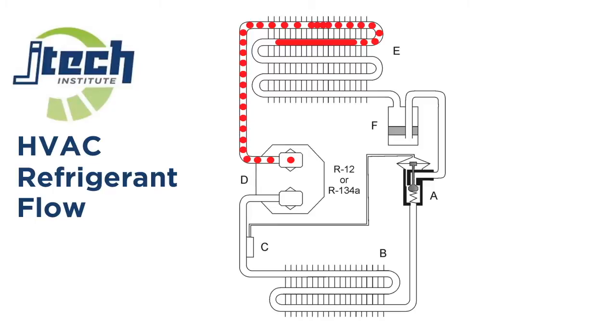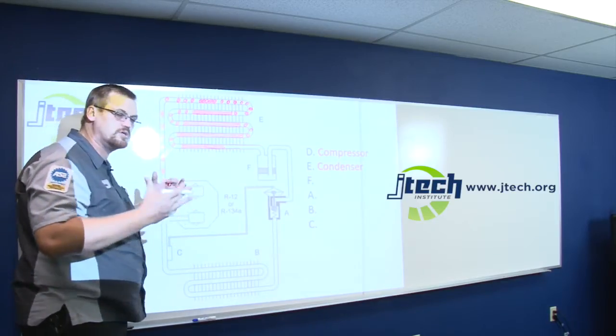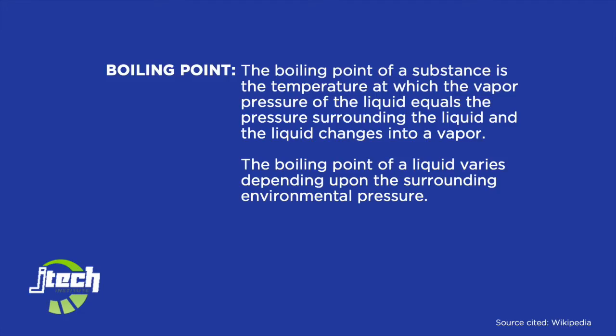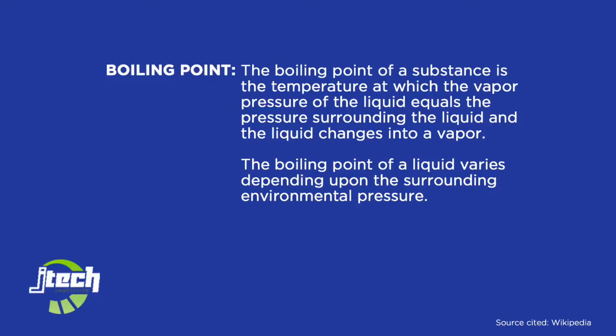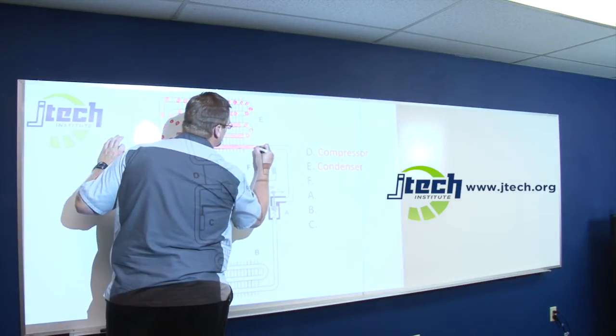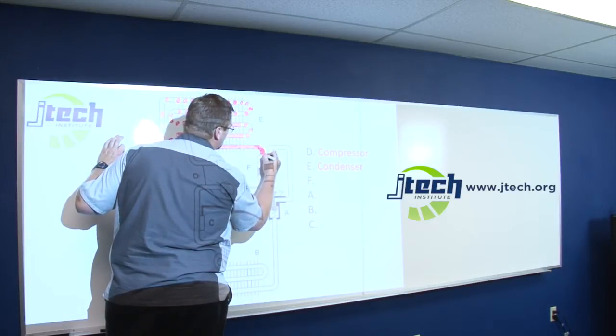All the way through this, we will be creating more and more liquid refrigerant. You can tell how well your condenser is operating by the point at which the temperature starts to drop again. At the very end of the condenser, we should be pure liquid, no vapor. Once we hit that pure liquid stage, that tells us we are doing what's called subcooling. Subcooling is in relationship to the boiling point, but below it — we are all liquid and lowering the temperature even colder than boiling point. The more heat we take out of the refrigerant in the condenser, the more heat we can take into the refrigerant later in the evaporator, and the better the system works. Coming out of the condenser is all high-pressure subcooled liquid.